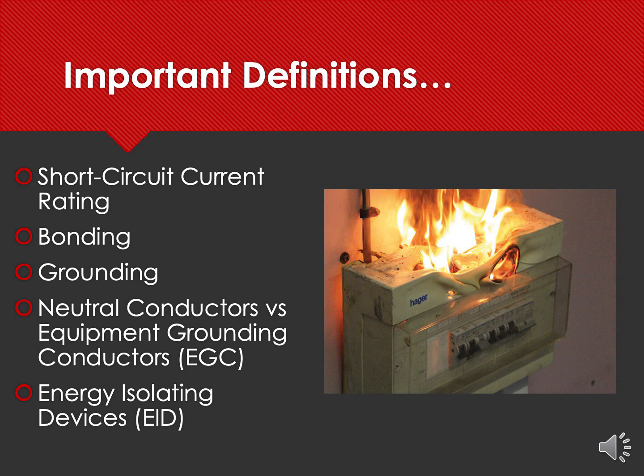There are a few definitions that we need to understand before we press forward with the presentation. The first definition is called short circuit current rating. Now we need to differentiate the short circuit current rating from the interrupting rating of a protective device, in that the short circuit current rating takes into account all of the equipment in the panel, not just the overcurrent device that protects the panel itself. So this is an important definition to keep in mind because we have to size the equipment appropriately to handle the weakest element in the system.